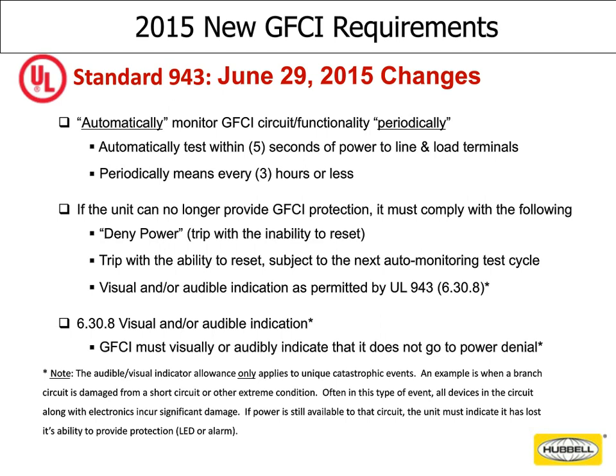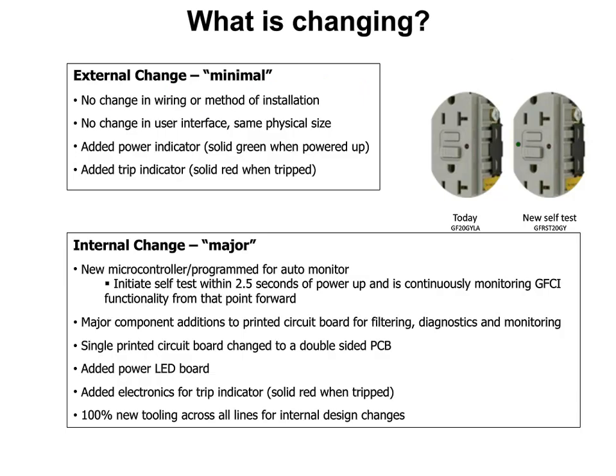So, again, two scenarios. 80% of the time it's going to trip, you're not going to be able to reset it, and you're going to be forced to change that device. In about 20% of the cases, it's going to flash a light or give you an audible signal to tell you that there's a problem. And again, this is a UL standard. Every product must have that.